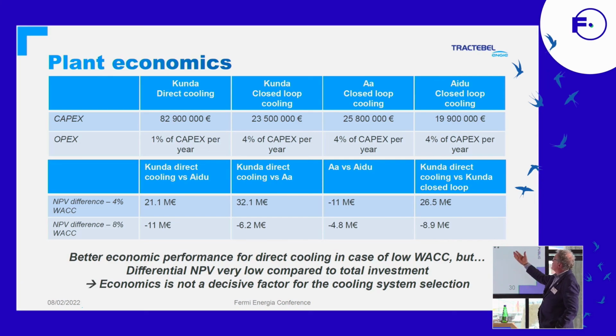When the value is positive, that means Kunda direct cooling is better than closed-loop cooling in Aidu, for instance, but it depends on the interest rate used for the WACC, the cost of money. With high interest rates, it's actually the reverse — closed-loop cooling is more economical. But overall, there are relatively small differences in terms of money between these cases; the differential NPV is very low compared to the total investment.